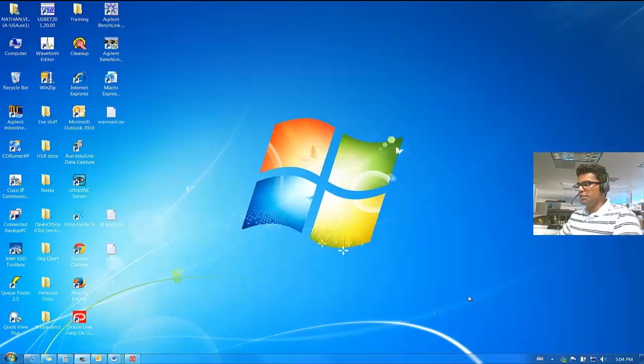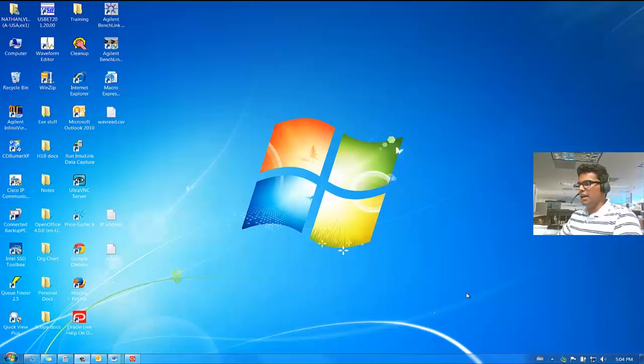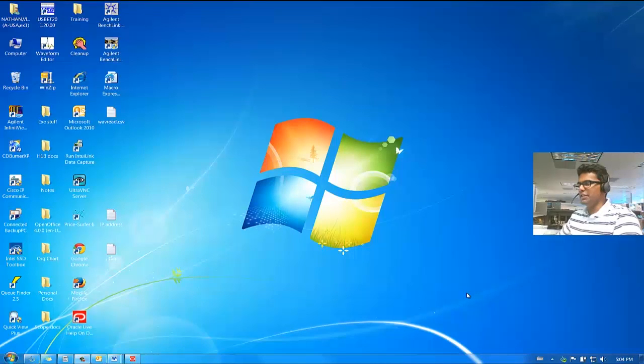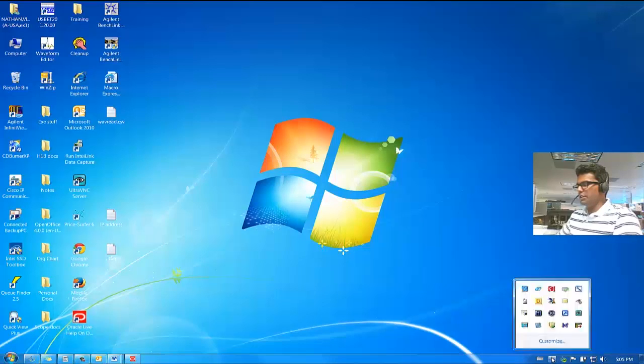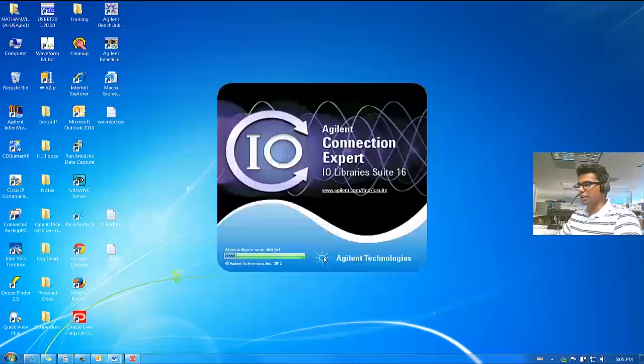Viewers, now we are going to set up RS-232 connection with the 34970A and LAN interface with the 34970A. First, open Agilent IO Connection Expert by going to your tray, right-clicking on the IO logo and clicking on Agilent Connection Expert.